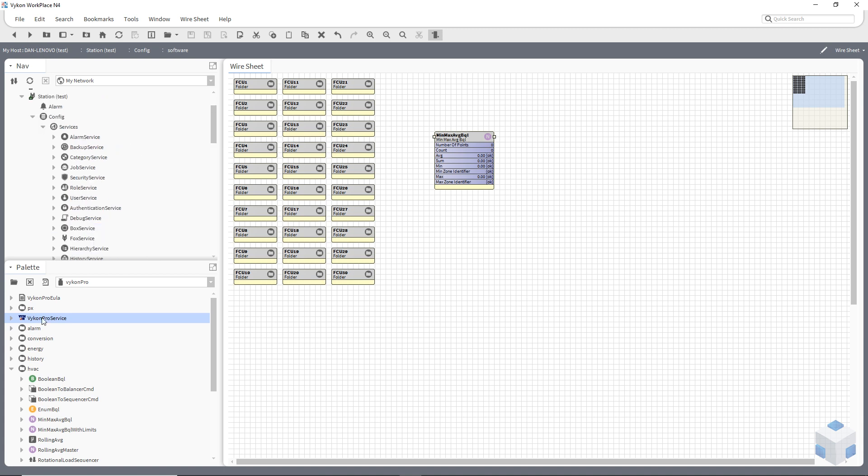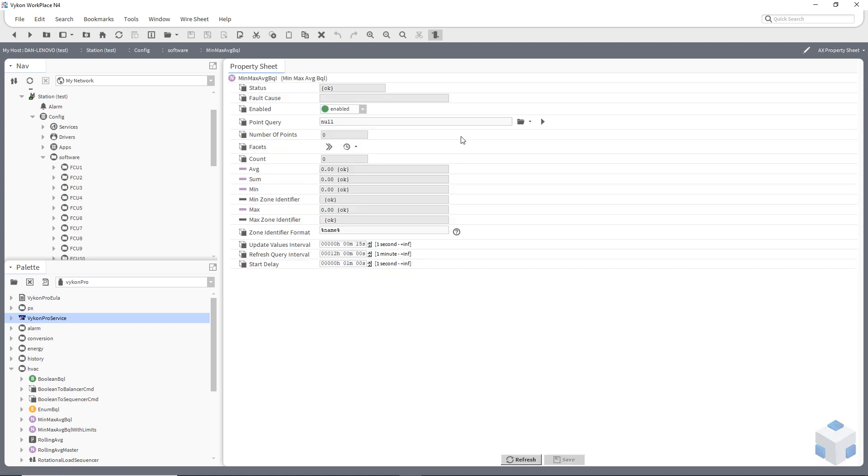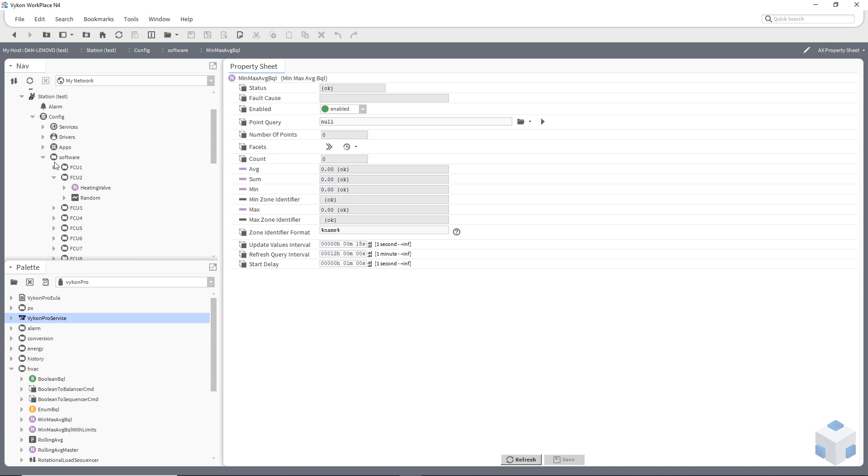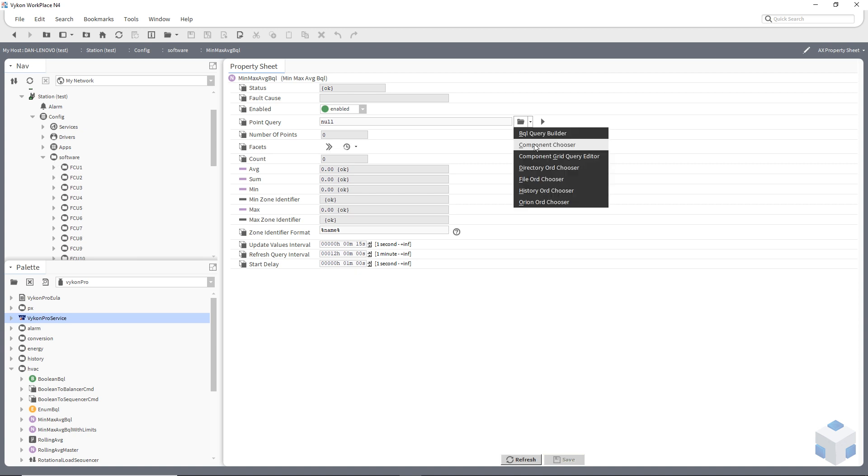I've actually already done this for my Vykon Pro palette and I'm going to go into my min, max average BQL. Now what I'm going to want this block to actually do is to actually use wildcards to look at a certain name. So within my fan coil units I've just made some pseudo points and I've called them heating valve. So I'm actually going to click this little point here and go BQL query builder.